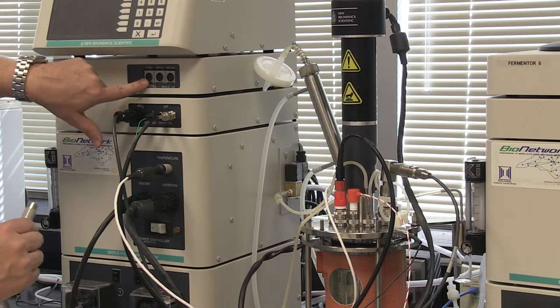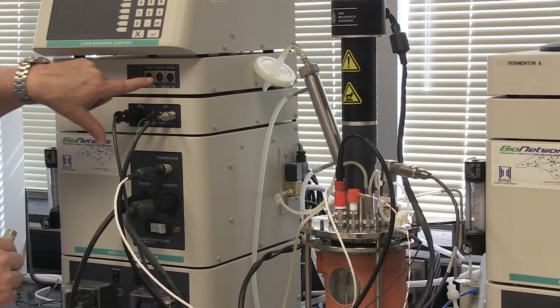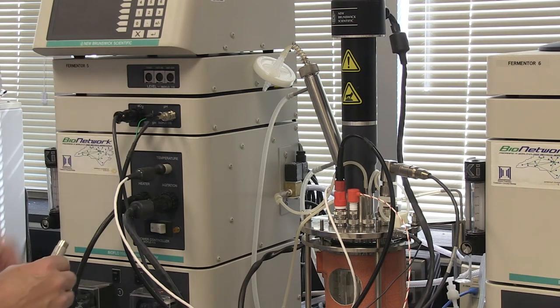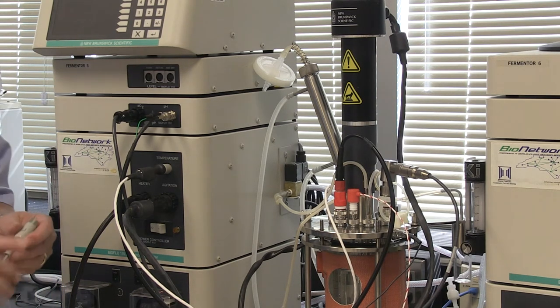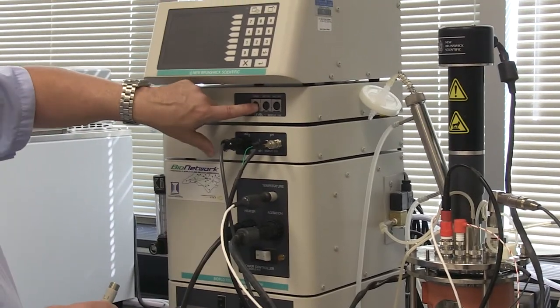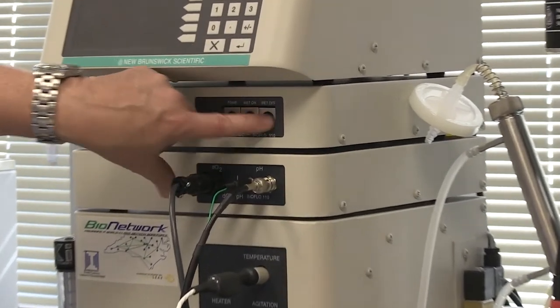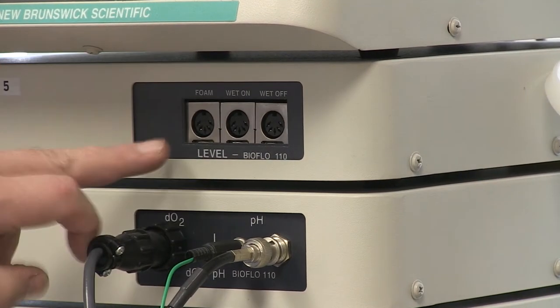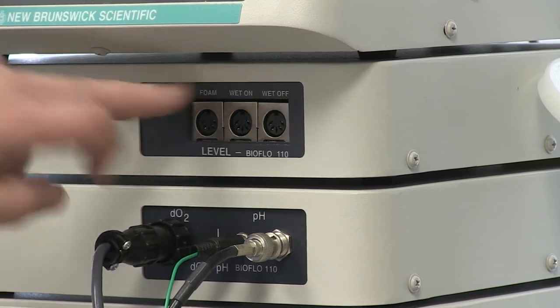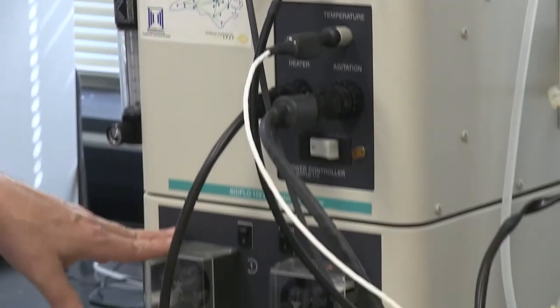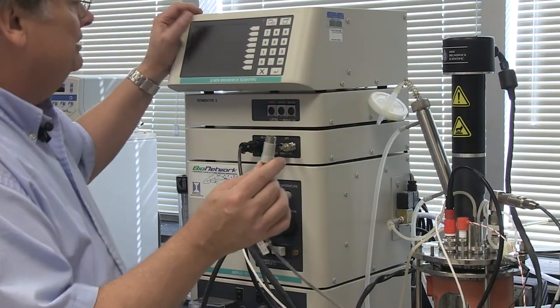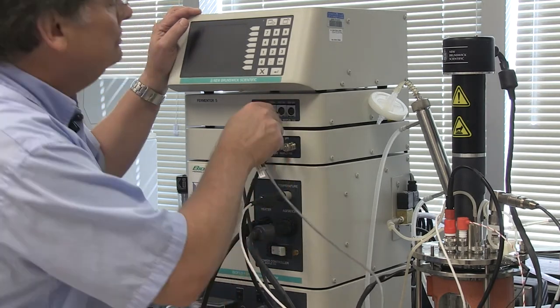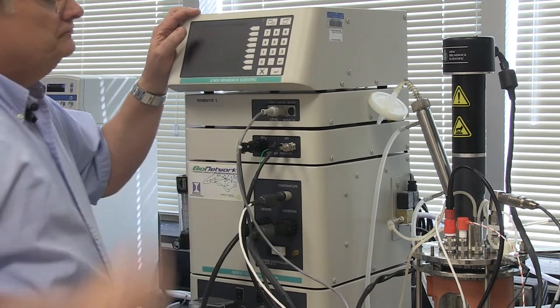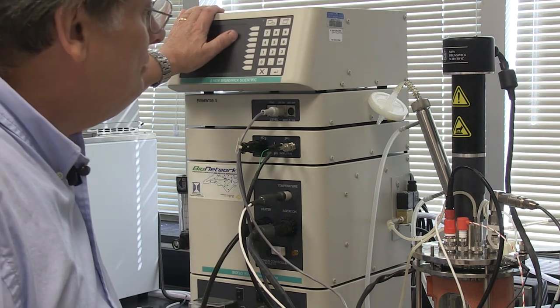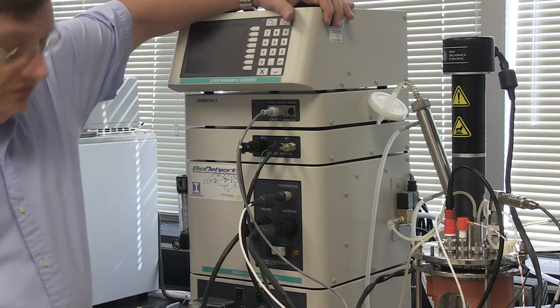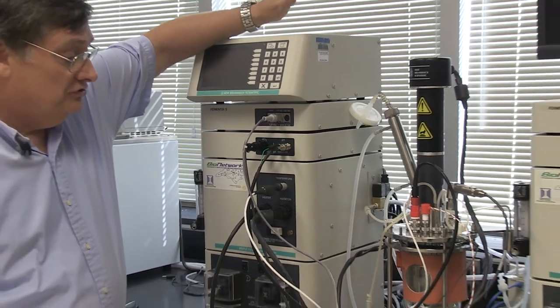And then you have three levels. It says foam, wet on, or wet off. Actually the foam is for anti-foam, and it would be a wet on also. And so what it's doing is it's controlling these pumps. If it says it's getting wet from the foam, it's going to turn on a pump that's going to pump anti-foam in. So just for the sake of this, I'm going to plug it into the wet on. Okay, so this is pretty much the connections for the standard operation that you'll be doing.